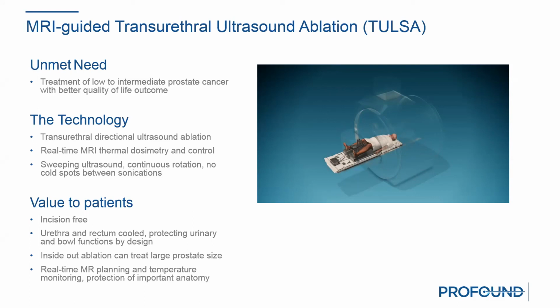From a value proposition perspective, TULSA was non-invasive. For patients, that's a benefit. They don't have to deal with the heal-up time. And it has a cooling method. When you're heating someone, you will burn good and bad tissues, so the cooling method protects critical structures. That was a value. And it could heat from inside the body. Usually HIFU treatments are from outside, focusing inside the body. This was unique in that sense.